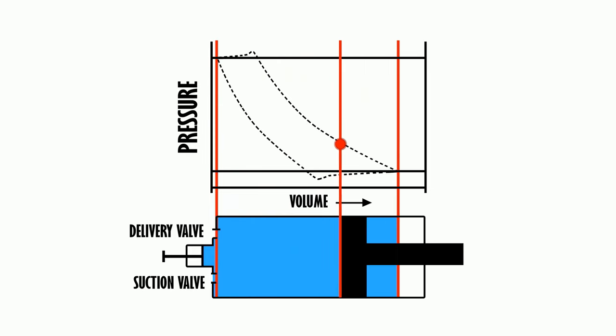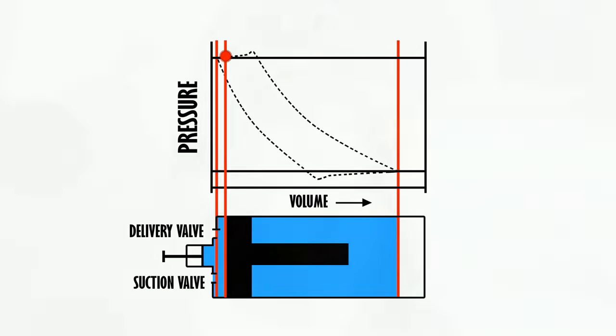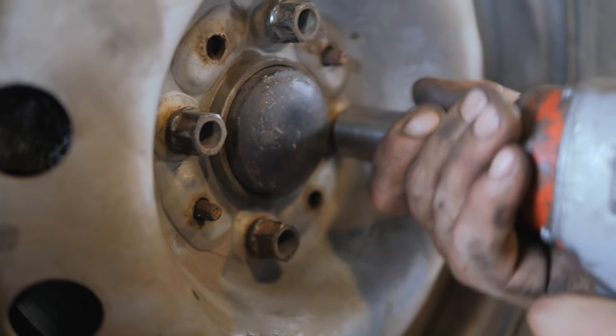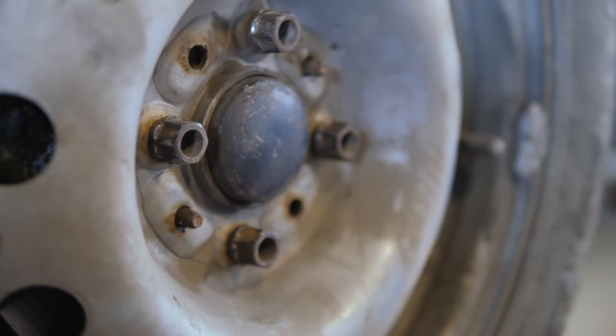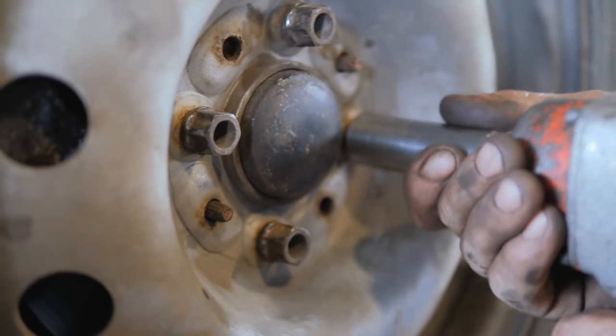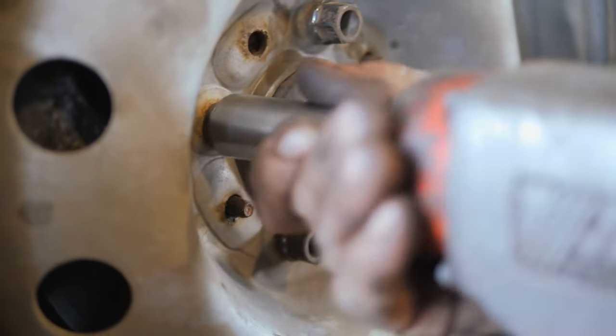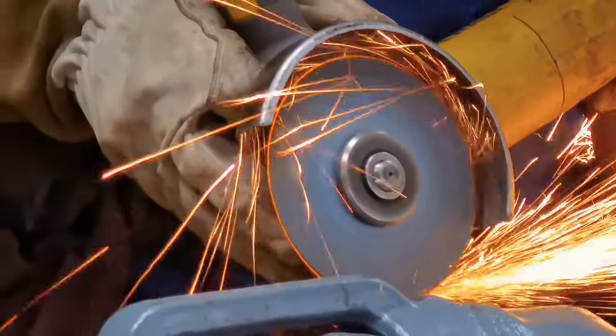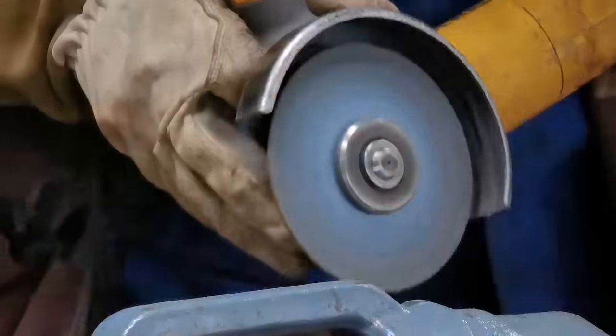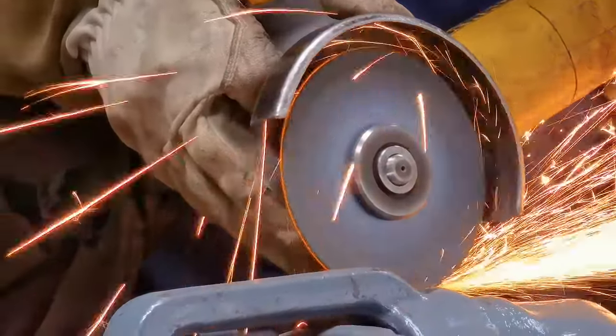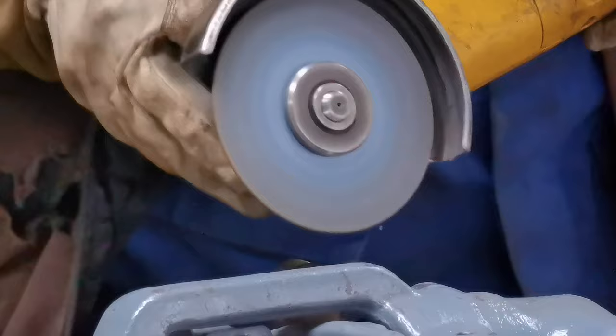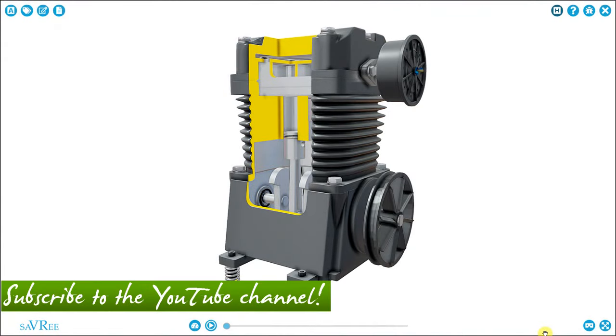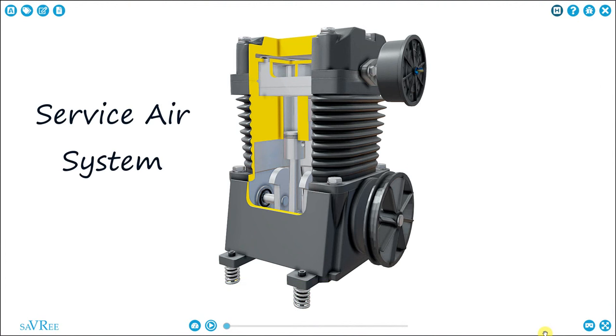We may compress air because we need to use it to power hand tools. You'll often see pneumatic hand tools in workshops, on building sites, in engine rooms, in industrial plants and things like that. The hand tools might be used for things like grinding, wire brushing, or for undoing nuts and bolts, although there are many other applications. If we're using compressed air for hand tools, we'll often call that compressed air system the service air system, and it will operate at around six bar, maybe seven bar, which is about 90 psi.